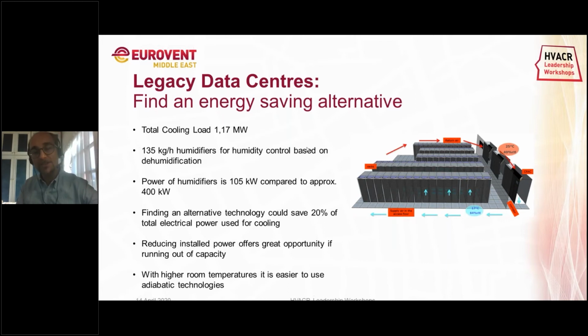But it's not only the energy that is the concern in this type of system. If you see the cooling power here, more or less it was using 400 kilowatts as installed power. In the same system, 25% of that power, and 20% of the total power, was used for humidification. So there is a great potential, and this is the other message.